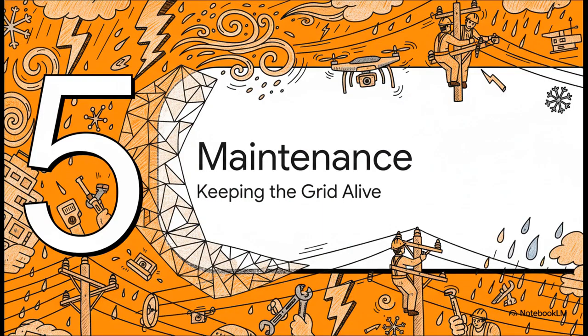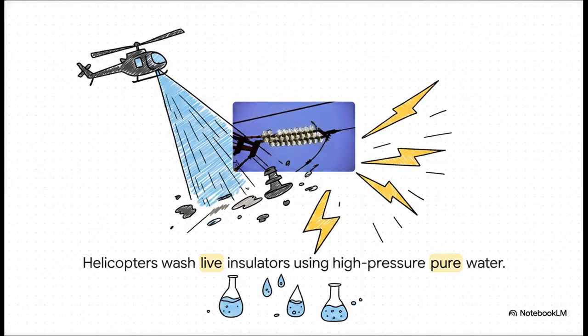All of this leads us to Section 5, insulator maintenance and protection. Let's see how grid operators actively fight back against these relentless natural forces. Because as you can imagine, you can't just install these things and forget about them. To combat all this buildup, we go to some pretty extreme lengths. I'm talking about deploying helicopters to pressure wash insulators dangling hundreds of feet in the air. But here's the absolute kicker. They do this while the line is entirely live. They don't shut your power off. How is that even possible?